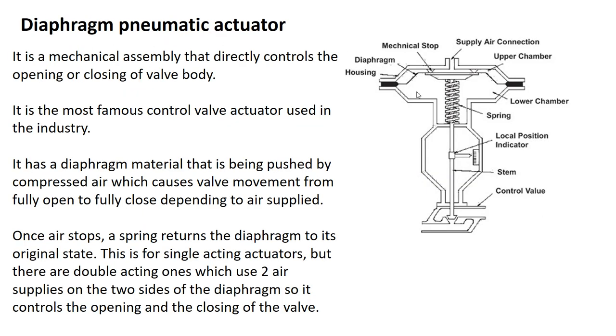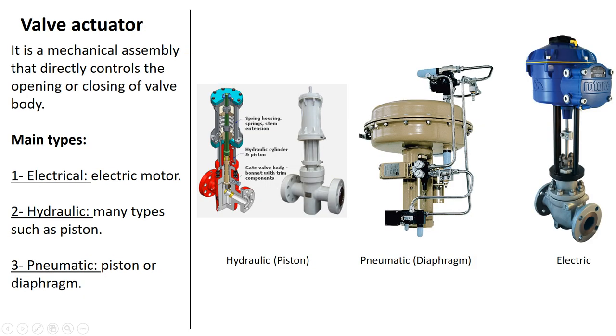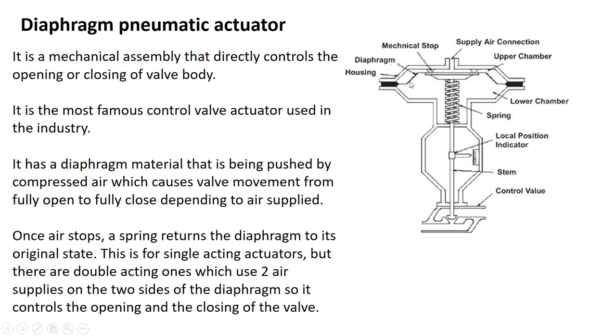Now the diaphragm pneumatic actuator — the diaphragm is like a rubber or elastic material. Air flows in through a hole and pushes it down along with a spring. With this being pushed down, the valve — a globe valve in this drawing — is pushed down or up according to the air supply. The spring acts as a reverse mechanism.